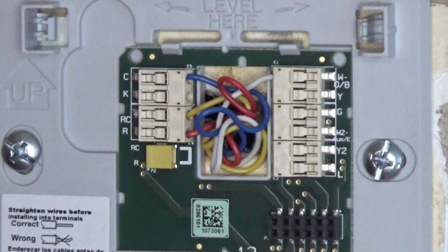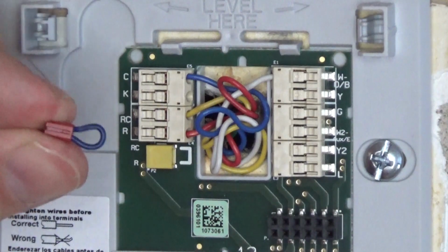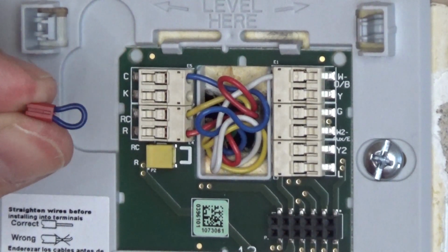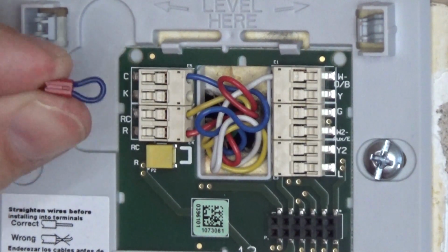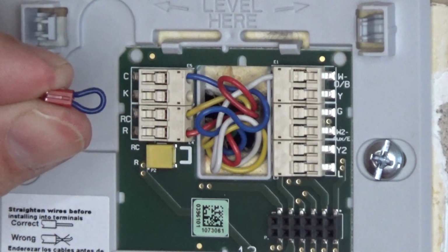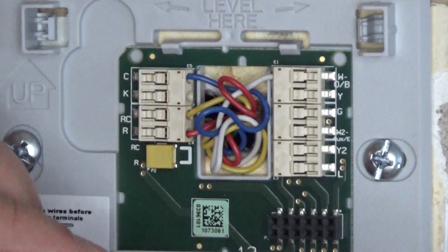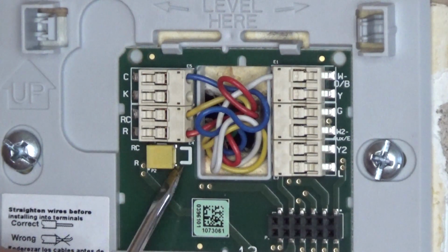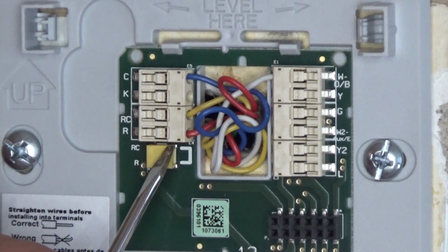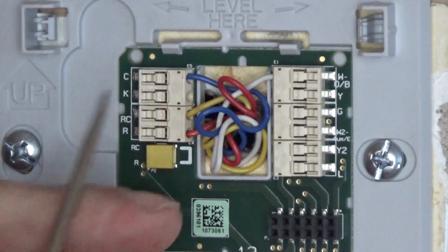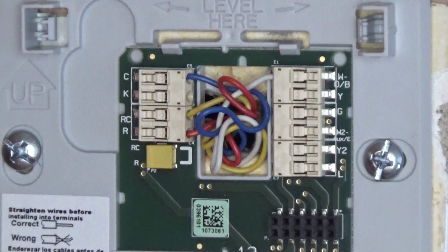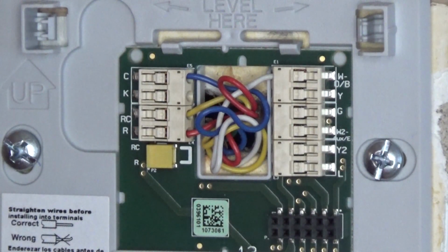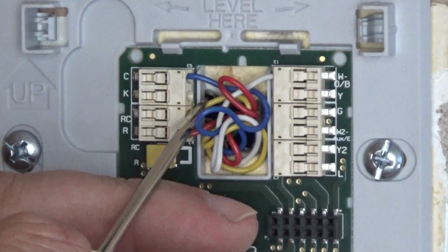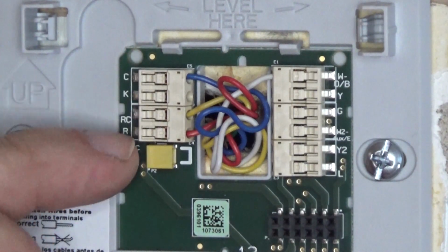The big important thing to note here is this right here. This is an R to RC jumper. You will need to pull this for this to work. This is connected over here. It's connected right there. My fingers are too big to show you it, but from the R to RC, that would feed this to this. Normally that would work fine, but like I said, when I shut off my boiler, I shut off the 24-volt transformer at the boiler and thus kill the system. So we pull this, and that's why we have to feed a separate RC. That's why they put it there.